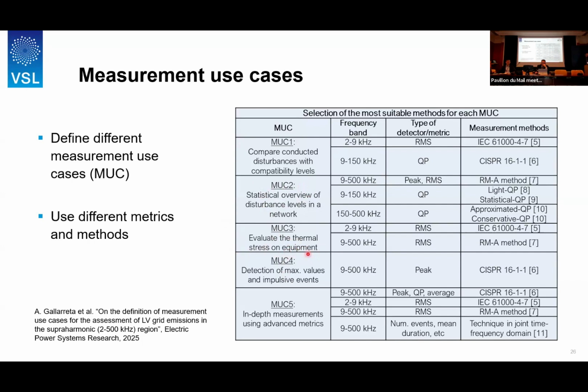You might also evaluate the thermal stress on equipment connected to the grid. So how sensitive is the equipment to heating by these higher harmonic components. You might detect maximum values in the case of impulse events, or some other metrics and in-depth measurements. And for all these measurement use cases, there are different frequency bands with different metrics. We have seen the RMS definition, like Deborah said, quasi peak or just a normal peak, and all these methods are actually defined already in either papers or existing standards. And I know this overview is in this paper, so you can look it up if you wish.